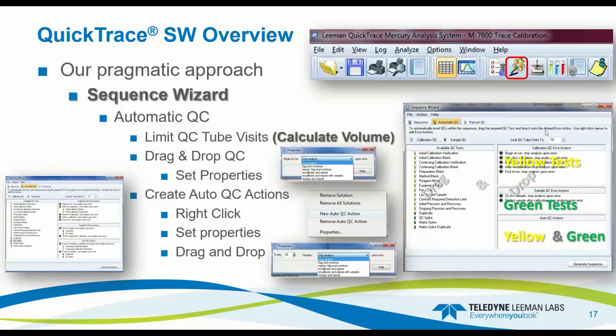One thing I must point out here that is really, really cool on this software is limit QC tubes. So for example, let's say you're pulling 15 mils of sample per analysis, which you never would be, but maybe you are. And then your tube is 40 mils. So you can only go in there twice, and then you'd be running dry. So if you know the flow, the volume of the tubes, and how many samples you're going to need, you can limit this.